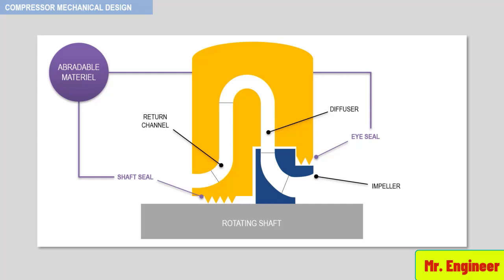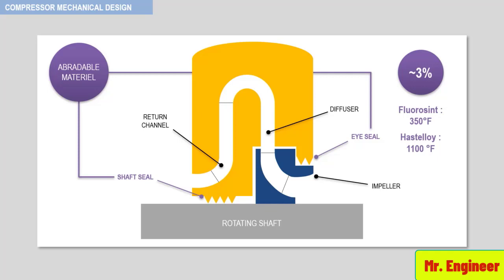Increases in stage efficiency as high as 3% have been obtained. Frequently used abradable seal materials are Fluorosint and honeycomb arrangements of Hastelloy. The temperature limits of these materials are 350°F and 1100°F.